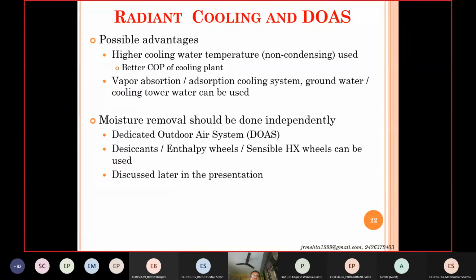So the possible advantages in radiant cooling systems, it is many times combined with, because radiant cooling cannot provide you the outdoor air or fresh air, which is required for keeping the pollutant content inside the room in check. You can't allow the pollutants in the conditioned space to exceed a certain level. So you have to take the air from outside, and you may filter it and clean it and then supply it into the conditioned space.